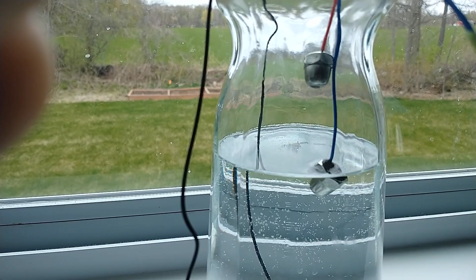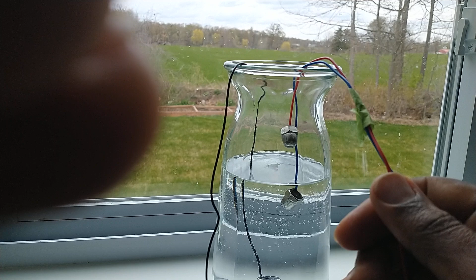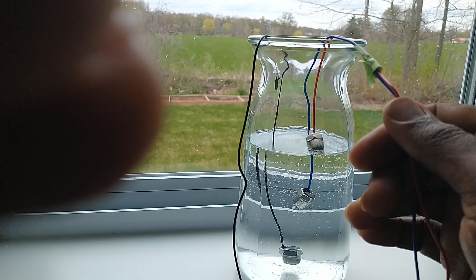I'm using my water until it goes below the blue probe, and the pump has gone on - you can hear the click. Now say the pump is pumping, the water is rising, it touches the blue probe, but it doesn't stop - the blue probe only declares there's no water. It's only the red one that should declare the tank is full. Listen, as it touches the water, you hear a click, then the pump goes off.